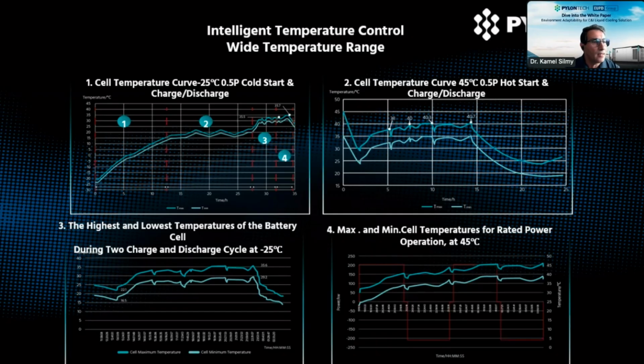So the system is designed so that even if the cells have a temperature of -25 degrees, the system will heat up the cells to 10 degrees Celsius to make sure that we can start to work and provide the energy to the customer. Phase 2 is the operation part, and this is the difference between the lowest curve and the curves above. This is the lowest cell temperature and the highest cell temperature. As you can see, the difference is very, very low. We have less than 5 degrees Celsius between the highest and the lowest cell temperature.